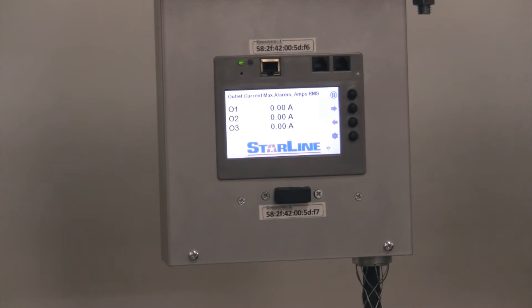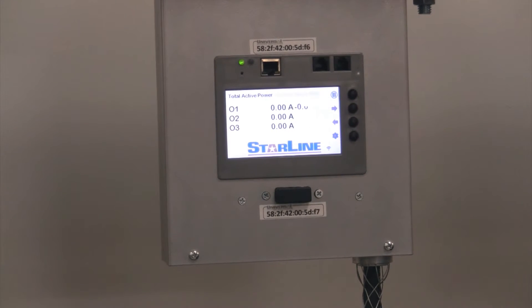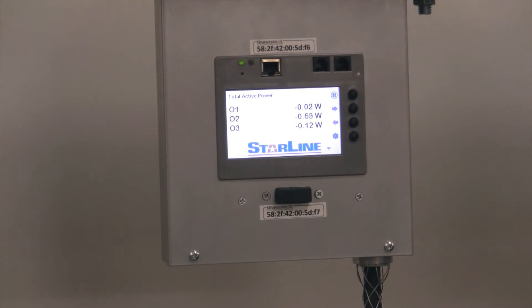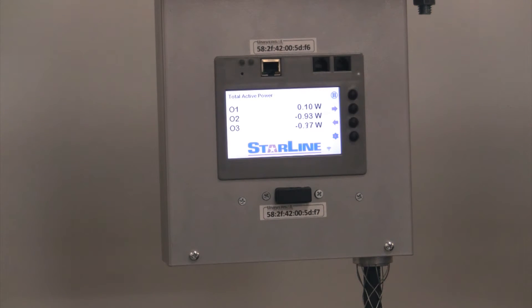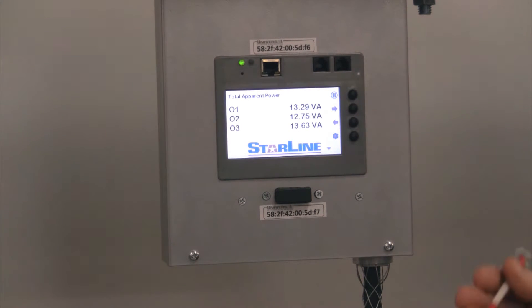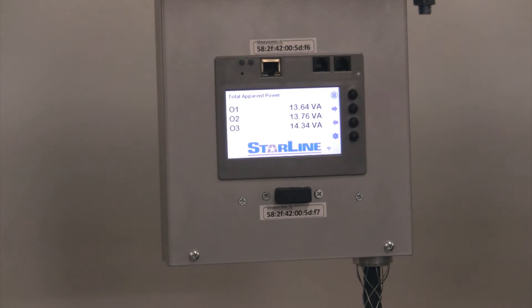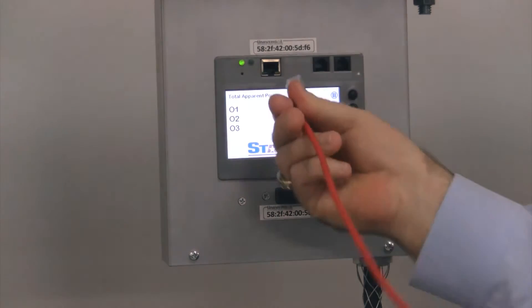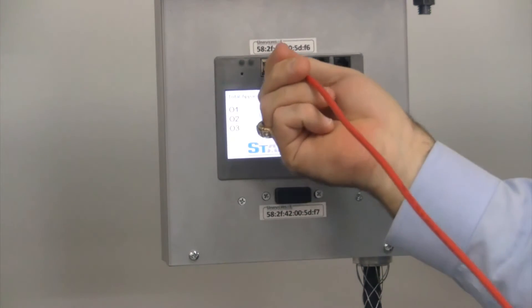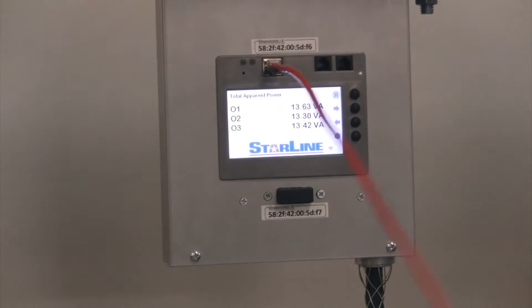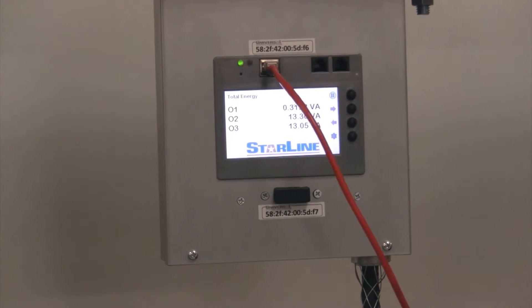For configuration of the integral webpage, you actually need to connect to the Ethernet port of the device. Since this is typically accommodated with a laptop, a crossover cable is needed to connect to the face of the Ethernet port in the meter. So as you can see here, I have a crossover cable, and we'll go ahead and connect that directly to the meter, and then plug that into the Ethernet port on your laptop.